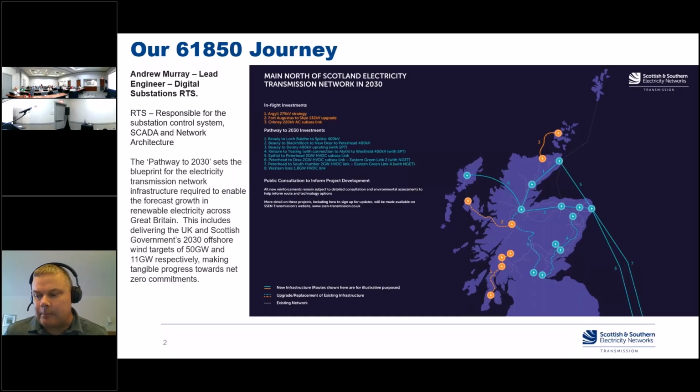and incomers. In the last 2 to 3 years, we've started to embark on our fully digital journey from station bus to include process bus and GOOSE. And today I just want to talk about how Test Suite Pro and some of the tools have helped us virtualize GOOSE and move on from a conventional hardwired delivery substation or partial station bus MMS solution to a fully digital solution that we're looking at. Actually, FAT and testing started just this week, today, so we're right there on the first tests of our digital substation.